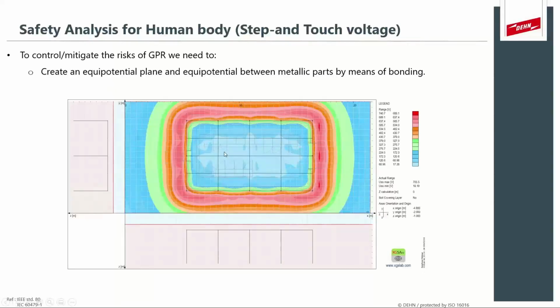So in the previous graphs, I actually showed you the ground potential rise you would see on surface level. And then this graph just shows the actual step voltage. So it shows the difference in voltage between points on the graph. And you can see the highest voltage difference is 740 volts, meaning that we do not exceed the 841 volt limit that we calculated as the allowable or the safety limit in our case. And that's because we have an equipotential plane with the way this grounding grid is meshed quite heavily.